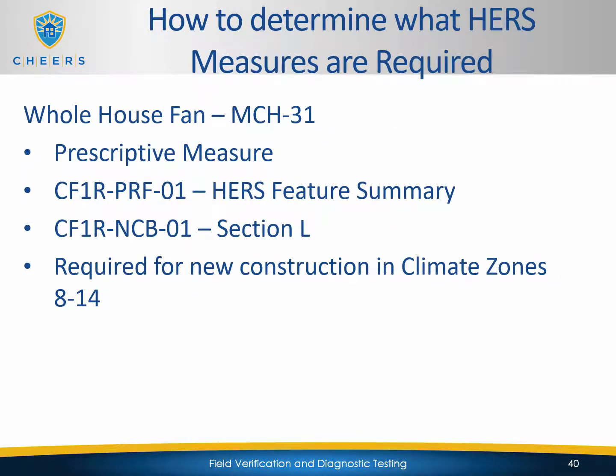Whole house fan on the MCH-31 is a prescriptive measure. So we're going to see that on either the Perf 01 in the HERS feature summary or on the NCB 01 in section L. And so whole house fans are prescriptively required for new construction in climate zones 8 through 14. So this would be a newly constructed home in one of these climate zones. A whole house fan is going to be required, and so you're going to find it in one of those two locations.